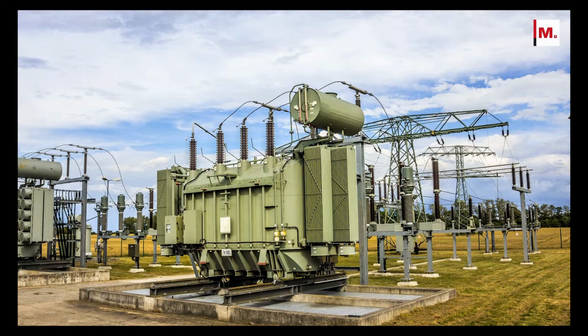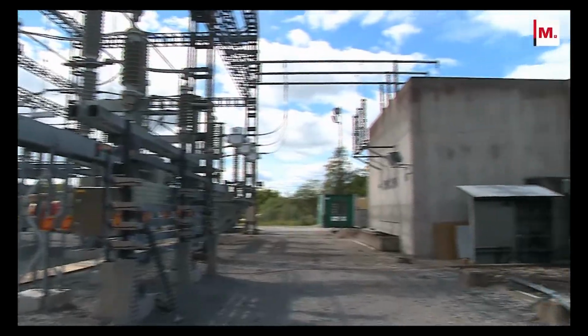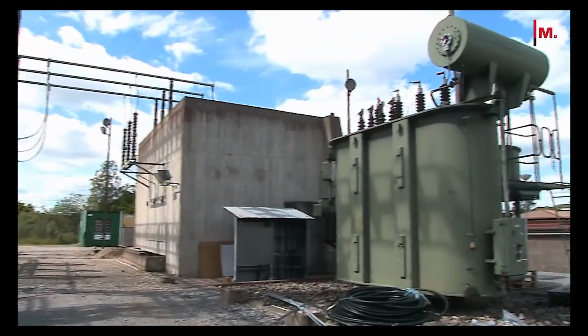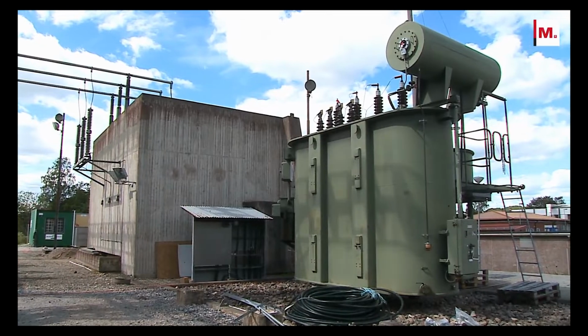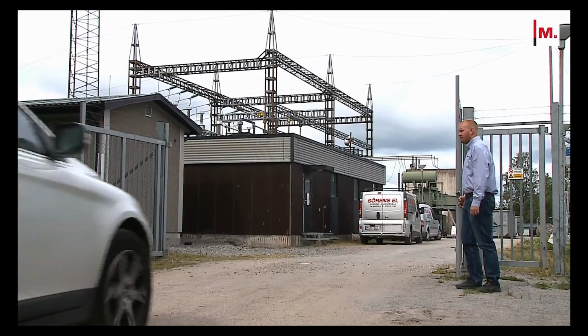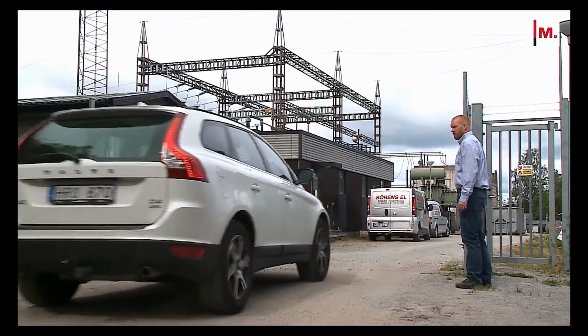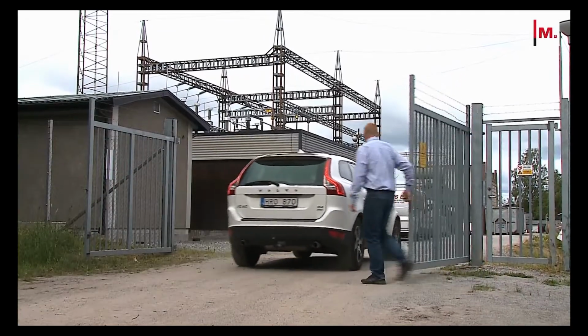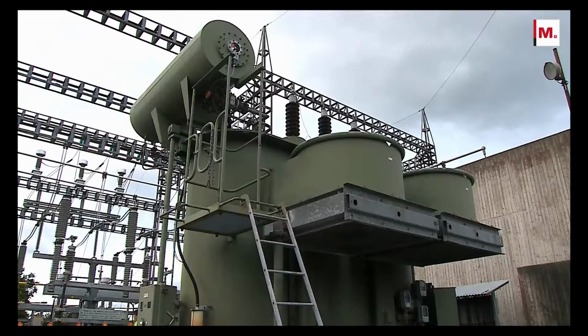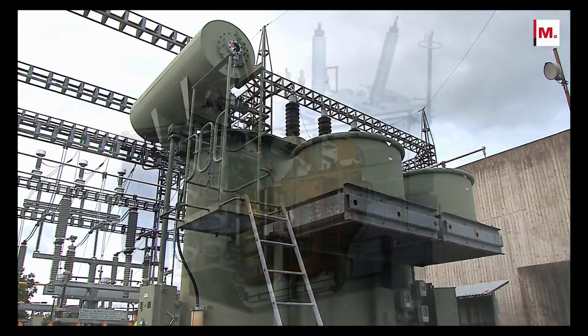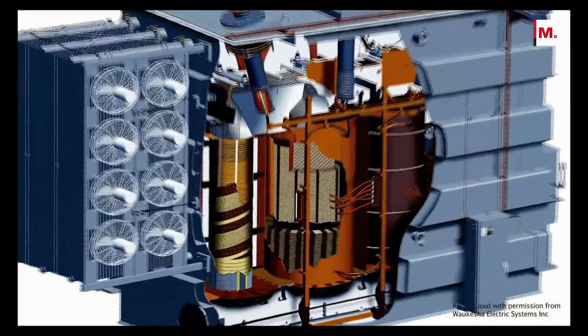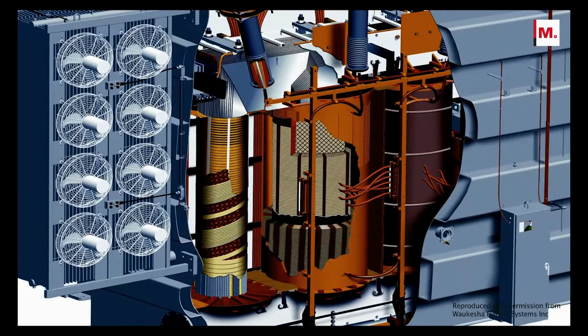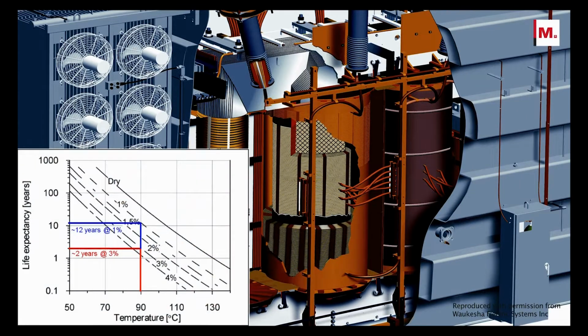Transformers and their bushings are important and expensive assets in electrical power networks, and they've become among the most mission-critical components in the electrical grid. Knowing the condition of the transformer insulation gives a correct input for risk assessments and asset management. Among other effects, high moisture content limits the loading capability, decreases the dielectric strength, and accelerates the aging of the paper insulation, thus reducing transformer life.